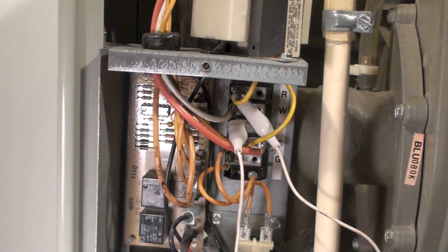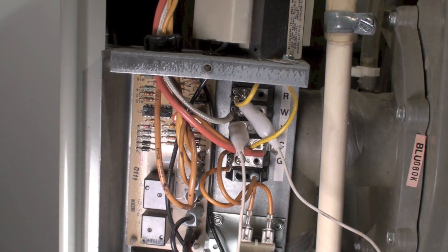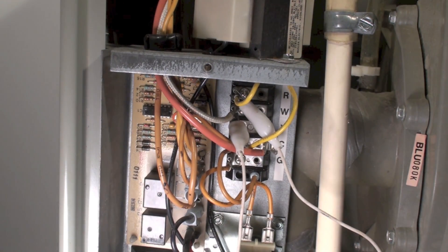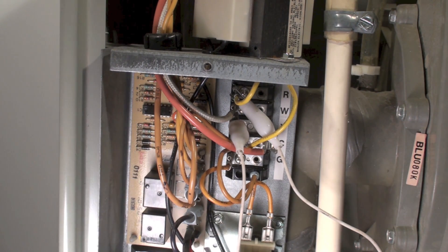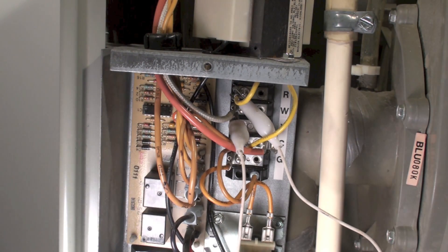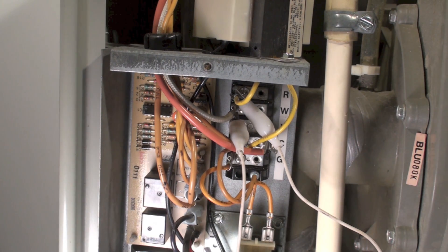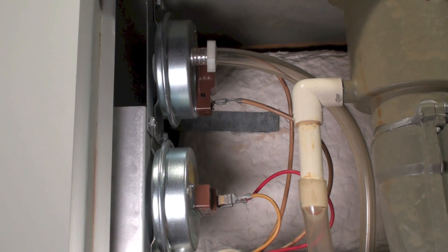It usually ends up being 10 or 15 seconds, as you saw it happen, and it goes to low fire. What's happening there is if the pressure does not drop to the point where that pressure switch is satisfied, then it doesn't go to low speed. That's kind of its way of adjusting for the vent length.